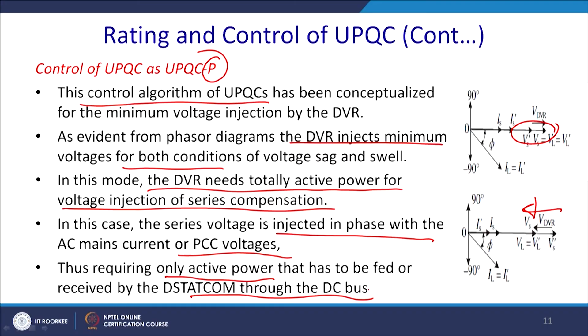And what happens then, it increases the current and thus the KVA rating of the D STATCOM. However, the KVA rating of the DVR is minimal in this operation mode of UPQC, UPQC P, because it only sees the in-phase component of the voltage. And in this case also the D STATCOM compensates the active and reactive power of the consumer load current, and all the current related problems with the harmonics.